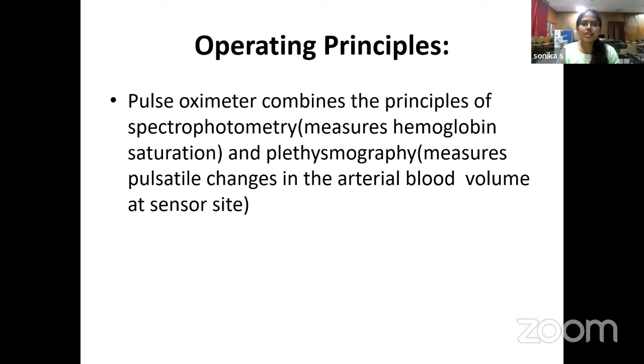First, spectrophotometry. As we all know, all atoms and molecules absorb specific wavelengths of light. This property is the basis for spectrometry. A pulse oximeter estimates SpO2 from the differential absorption of red and infrared light in the blood. As we can see in this diagram, we have two wavelengths. One is 660 nanometer, another is 940 nanometer. 660 nanometer is the red band, 940 nanometer is the infrared band. At 660 nanometer, deoxyhemoglobin, which is shown in the blue line, absorbs more, whereas at 940 nanometer, oxyhemoglobin absorbs more. The pulse oximeter computes the ratio between these two signals and relates this ratio to the arterial oxygen saturation by an empirical algorithm. So spectrophotometry is based on the Beer-Lambert law.